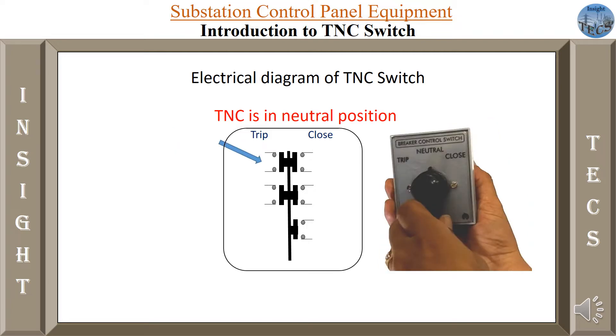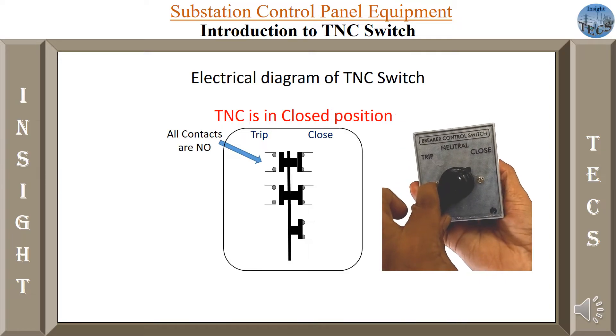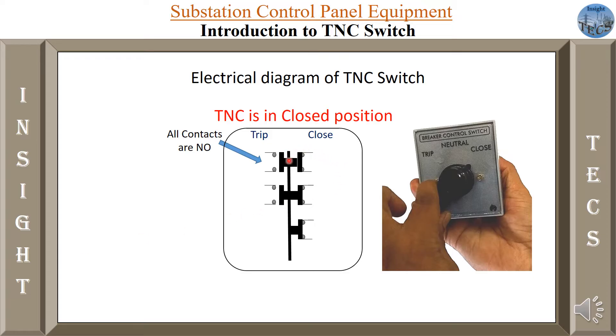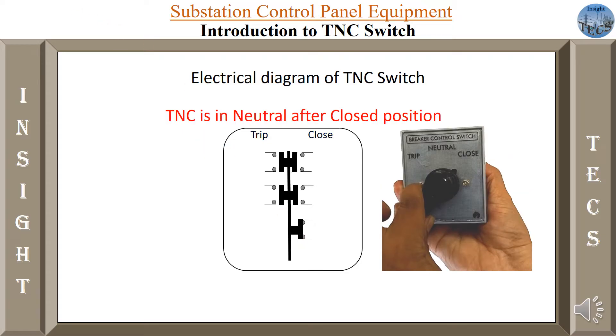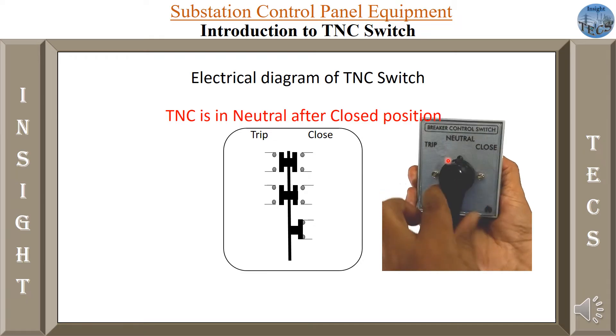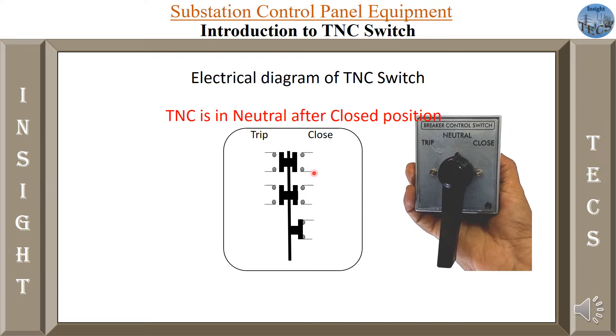Now let us see what happens when we close this switch. When you close this switch, the NO contacts become closed — they become NC contacts. Once you bring the switch back from close to neutral position, these NC contacts again become NO contacts. But there is a third contact, which is used for auto-reclosing mode. Even after closing, when we come back to neutral, this contact remains NC — it has not become a NO contact.